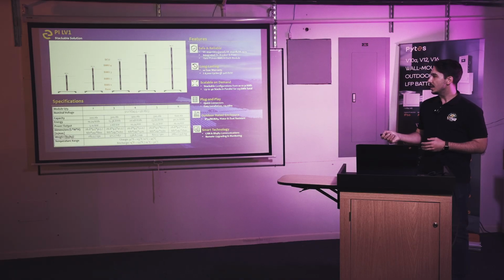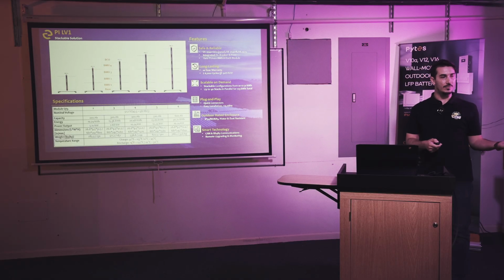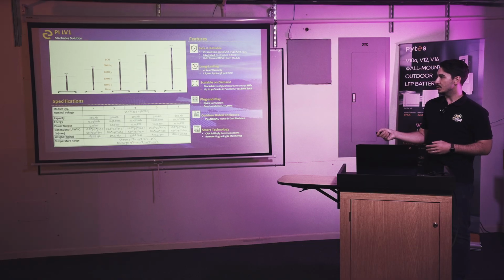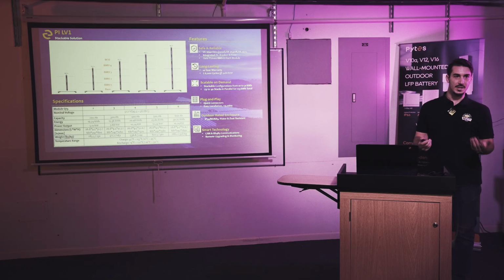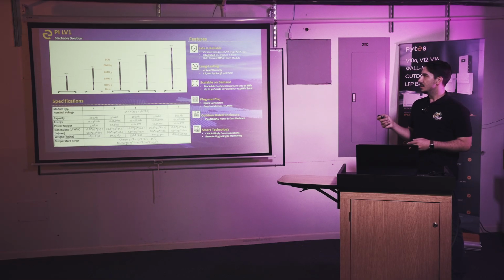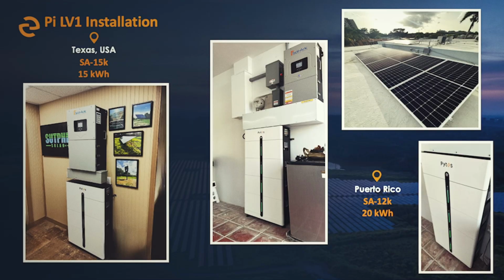So if you need 30 kilowatt hours for your Solar 15K, you need 6 modules no matter what, but you can't really put all 6 in one stack. Because 6 together with 1 BCU only gets you 10 kilowatts, which isn't going to satisfy what that solar converter wants. So the solution is you break those 6 modules into 2 stacks, and now you've got 7.7 times 2, just over 15 kilowatts total. That's how you unlock additional power output with this solution, by making another stack.